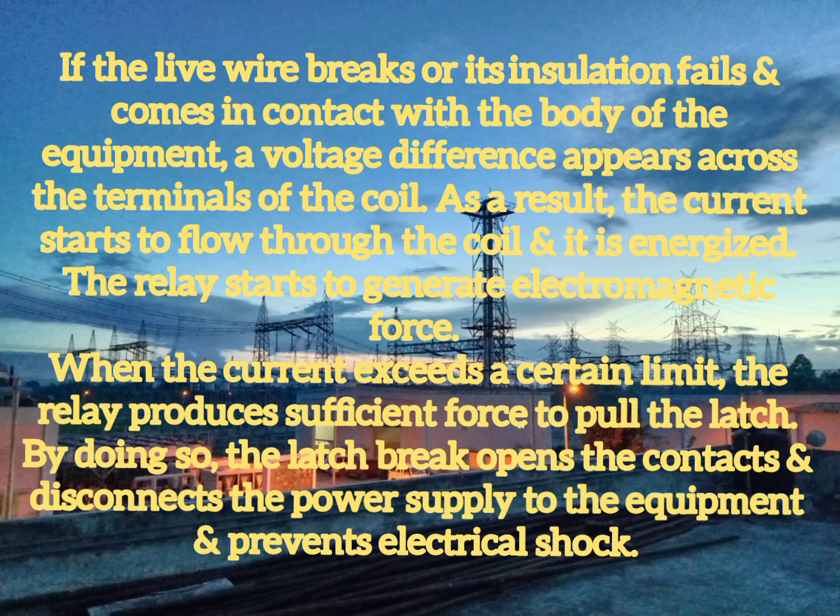So if the line wire breaks, or if its insulation fails and comes in contact with the body of the equipment, there is a voltage difference across the terminals of the coil. As a result, current starts to flow through the coil and it is energized. The relay starts to generate electromagnetic forces.